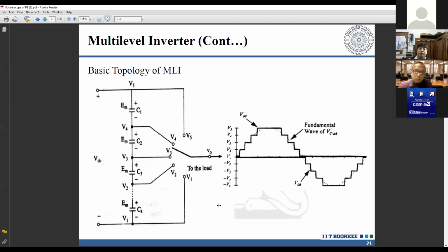So what do we reduce? We reduce the dV/dt, because a square wave has high dV/dt, and there is capacitance between ground and any body. This causes huge body currents through the capacitor, unnecessary losses, and insulation damage over a few years. We also have to de-rate capacitors because of harmonic presence.